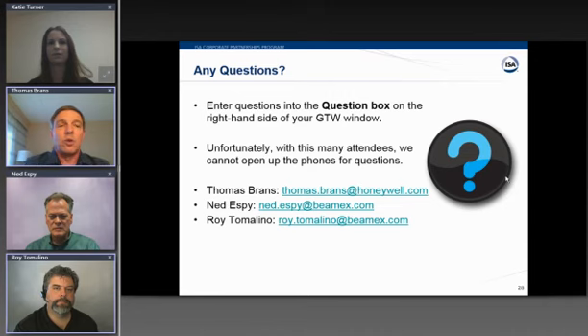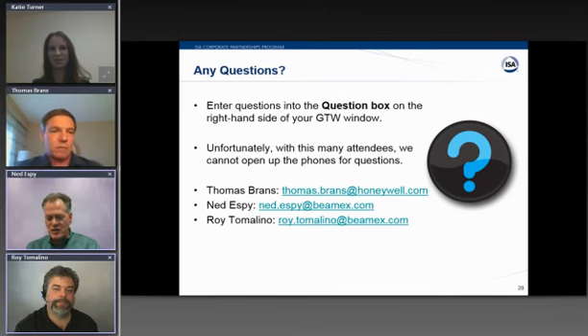Now, once an instrument's been calibrated, then you may want to range its output. So if, for example, a typical output is 4 to 20 milliamps, and if initially your 4 to 20 milliamps is scaled or ranged to be 0 to 100 degrees C, you may want to come back later on to re-range it to say 0 to 150 degrees C equals 4 to 20 milliamps out. So in fact, calibration and ranging are different things. But a long time ago with pressure transmitters, they actually used to be the same thing, but we won't go there. But guys, you want to add to that? No, I think that's pretty good. When you're using the communicator and you re-range it, you're not checking it against a traceable standard. You're just configuring. So they are different procedures. True. A communicator has no ability to actually measure.